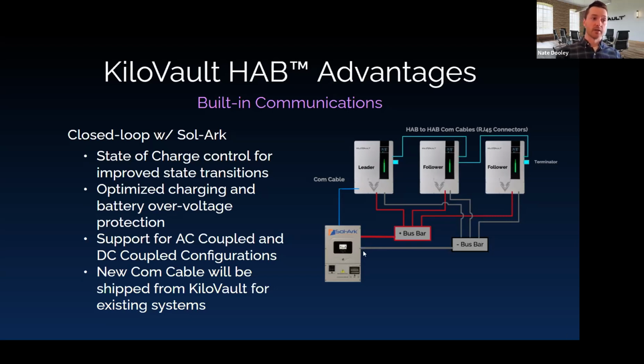This is really helpful because in normal system setups, the inverter is only able to see the battery voltage at these DC terminals, which is obviously not the exact voltage you're going to see because of voltage drop, depending on your wire run and how your conductors are sized. It adds a lot of efficiency and improved performance to the system if the batteries are able to tell the inverter directly: here is my state of charge, here is how I want to be charged, and here are the limits you need to set for yourself to disconnect before I ever have to.